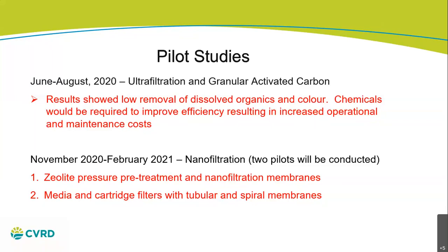So we've lined up two pilots that use different arrangements for nanofiltration. Nanofiltration is a very, very, very sophisticated membrane type of treatment. And we're very confident that we'll meet the requirements, being a step up from ultrafiltration. But still, we're going to run these two pilots and different arrangements for those pilots to confirm that it actually works and doesn't have other problems, like, for example, blinding of the membranes or anything else that could occur based on our actual water source from Stocking Lake.